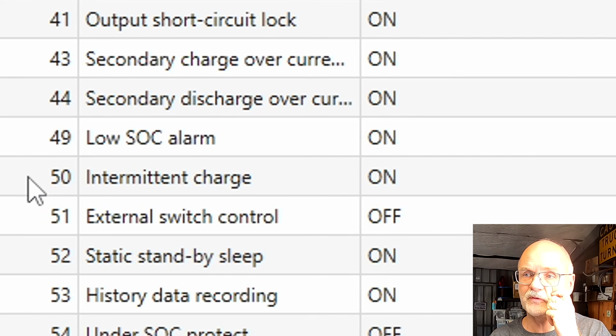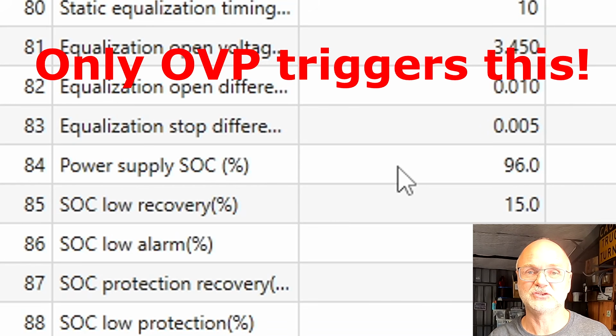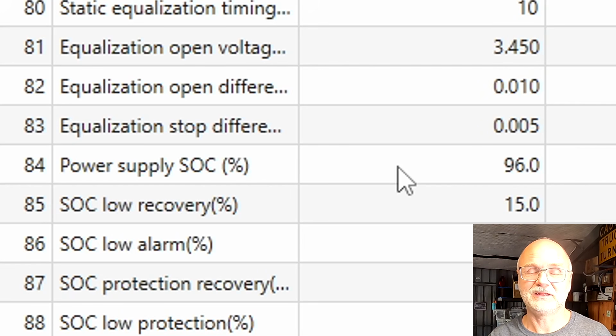There's also function switch number 50, the intermittent charge. If this is on, the function is turned on. The problem is, to trigger this, you need an over voltage protection situation, either pack or cell. One of your cells needs to hit 3.65 volts, or your whole pack needs to go over 58.4 volts, and that triggers the gap charging functionality. You can see how many compromises you need to go through with this BMS to make it somehow work. It's not clear what's happening. There are so many functions and features here, it's very hard to keep track and set the parameters correctly.